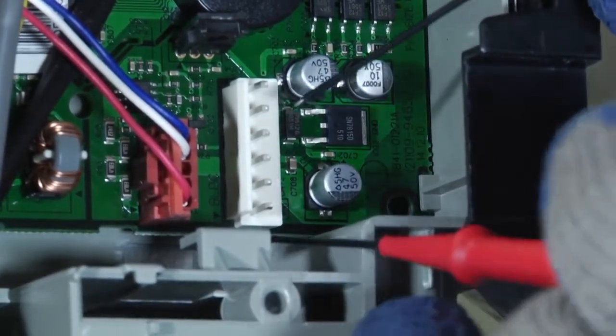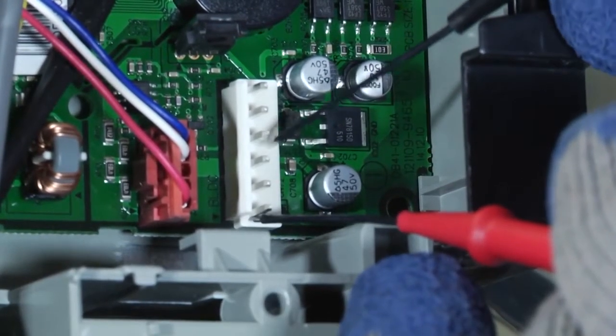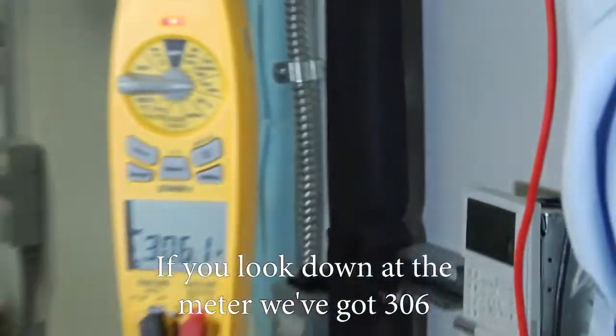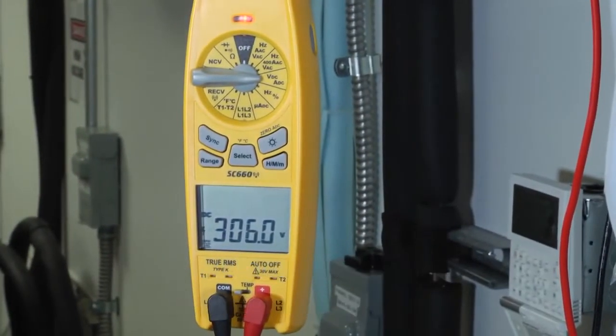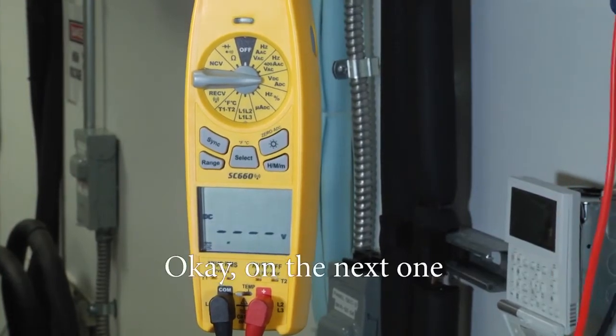If you look down at the meter, we got 306, which is a good DC link reading.